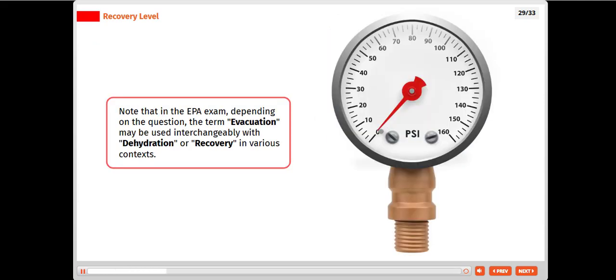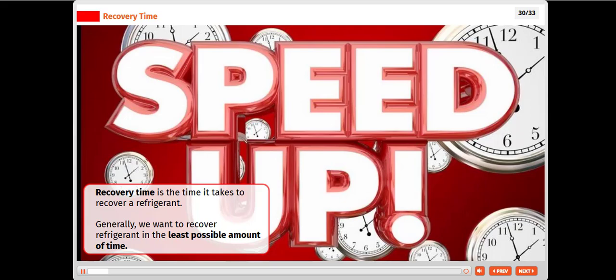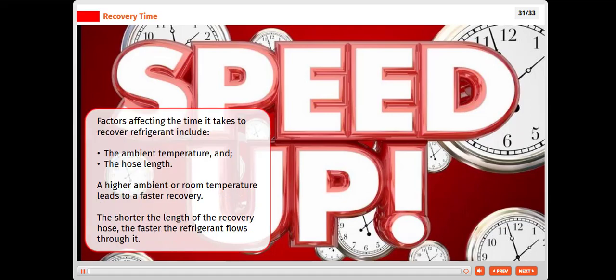Note that in the EPA exam, depending on the question, the term evacuation may be used interchangeably with dehydration or recovery in various contexts. Recovery time is the time it takes to recover a refrigerant. Generally, we want to recover refrigerant in the least possible amount of time. Factors affecting the time it takes to recover refrigerant include the ambient temperature and the hose length. A higher ambient or room temperature leads to a faster recovery. The shorter the length of the recovery hose, the faster the refrigerant flows through it.